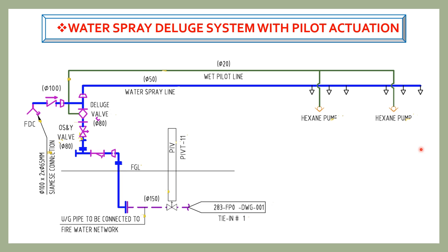The network is connected from the pump room through underground piping equipped with an underground gate valve and post indicator, then connected to the above-ground deluge piping. Before the deluge valve, a gate valve and a strainer are installed to ensure clean water flow and to facilitate maintenance. Another gate valve can be used above the deluge valve. The FDC connection links to the deluge network, and a check valve must be used in the FDC line.